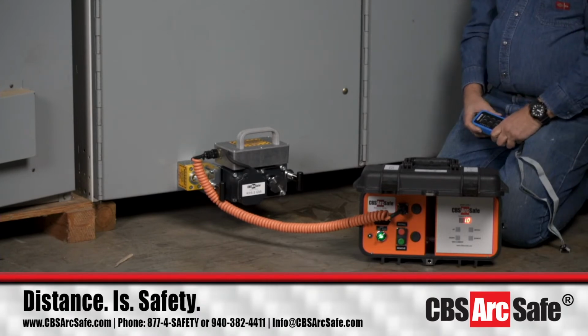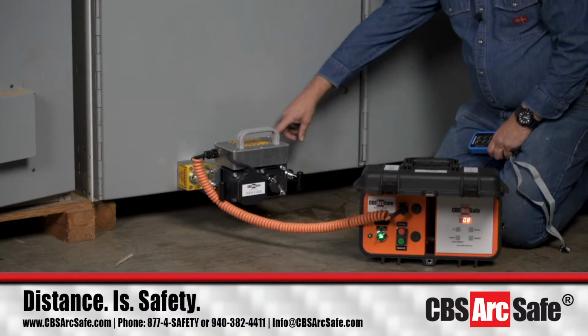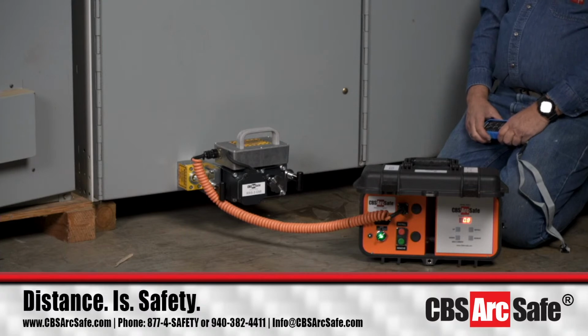Can you talk about how this device knows when to stop? Now the RS04 works on torque. So it's looking at the torque that's required, and so it usually takes less torque to bring a circuit breaker out than in. And so we put a torque limit on the low end and a torque limit on the high end for racking the breaker. We also have a mechanical clutch back here that you can't see, but I will show you when I take it off.